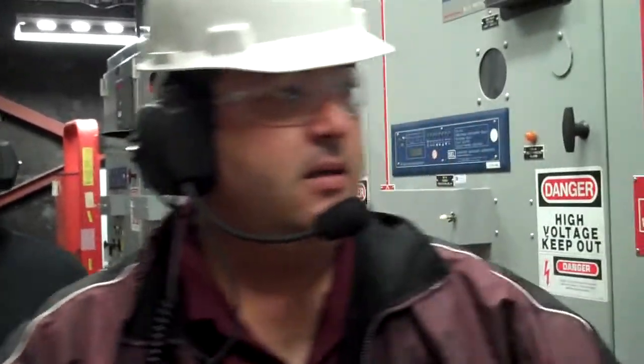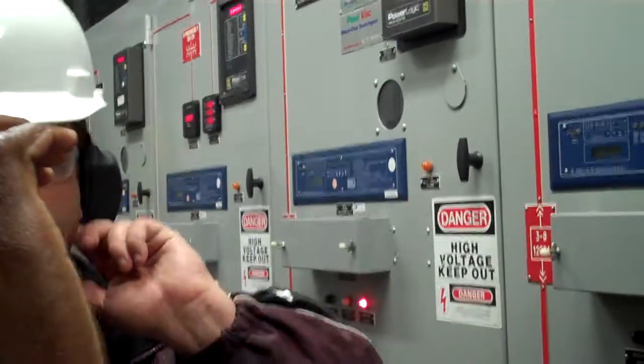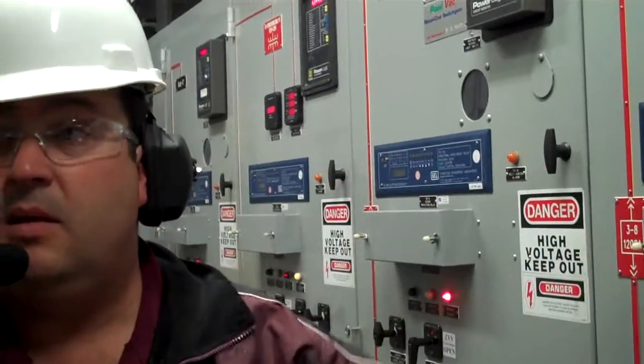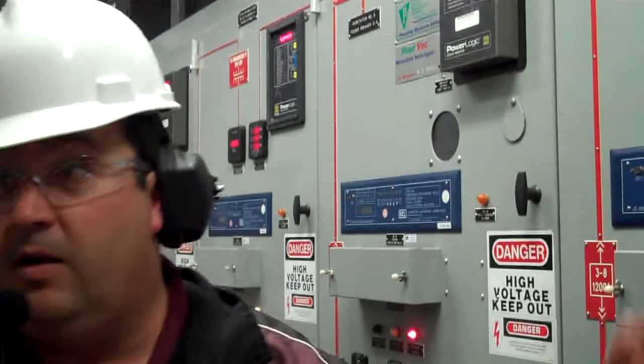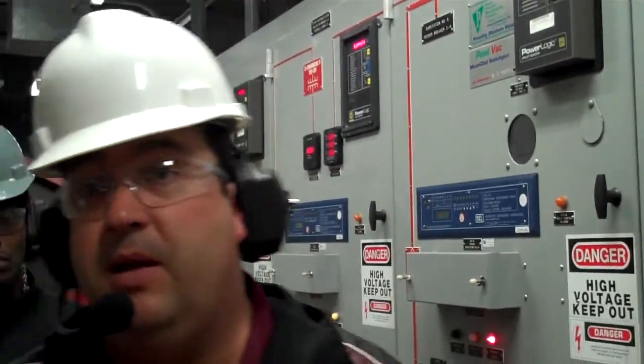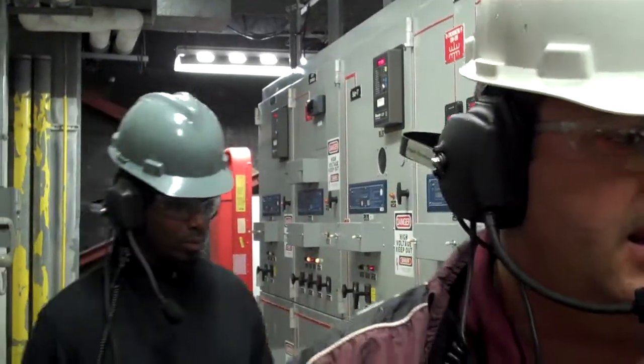So it means that there is no redundancy on the relays. Yeah, if the relay fails, the breaker doesn't trip. We get an alarm, we come down, and we program the new one. They don't fail often. They're very good. But I think since I've been here, we've had maybe 3 failures. Normally it's the power supply that fails. So if a relay fails, there is the differential protection on the bus if it gets out of hand.